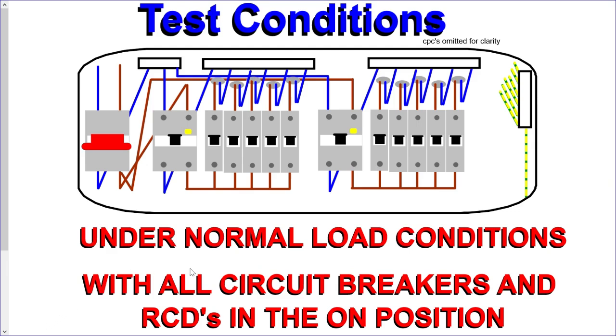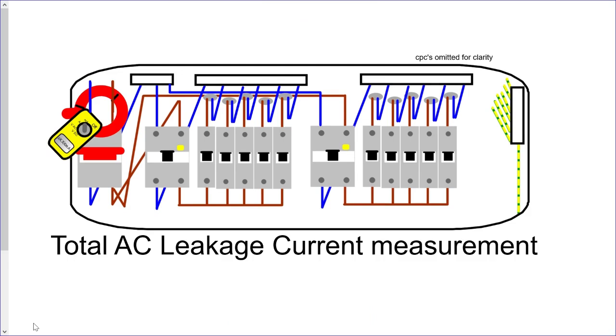Well, we carry out this test under normal load conditions with all the circuit breakers and the RCDs in the on position. We're wanting to see how this installation is actually performing. And it's pretty straightforward, the tests. We just current clamp the incoming supply cables. Either that will be at the top of the main switch or maybe before it goes into the local isolator from the DNO, if there is one there. And we take a note of the AC leakage current.